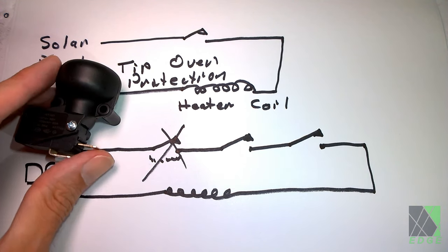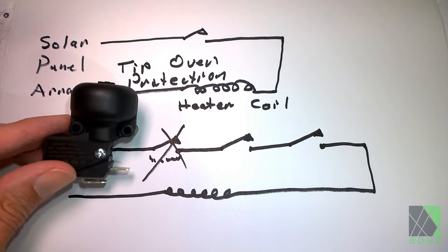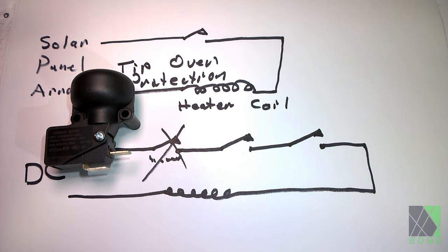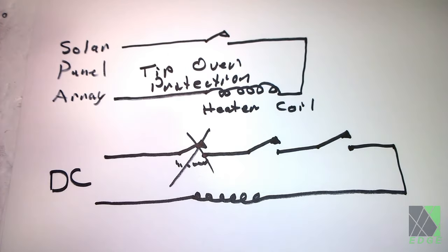But if you put more than one switch in series, you're guaranteeing a circuit interrupt. You're guaranteeing that if a switch fails, it's still going to turn off the heater. And best of all, there's no electronics. It's purely electromechanical, and it's easy to understand. Who doesn't understand if you put two switches in series, if one of them fails to open, the other one will still open the circuit. And, of course, you could always just completely remove the original switch and use two of these tilt switches.